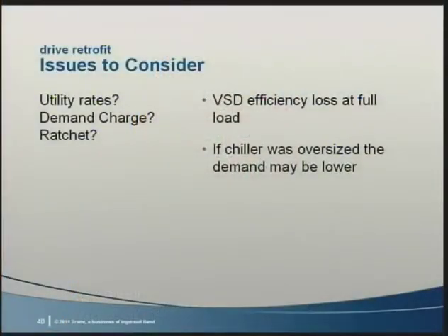First, as far as the utility rates are concerned, ask, will the increased demand cost very much? Be sure to determine how large the demand charge is and if there is a ratchet that applies that demand to all months. If there is, it may be possible to limit the maximum demand through the unit controls.